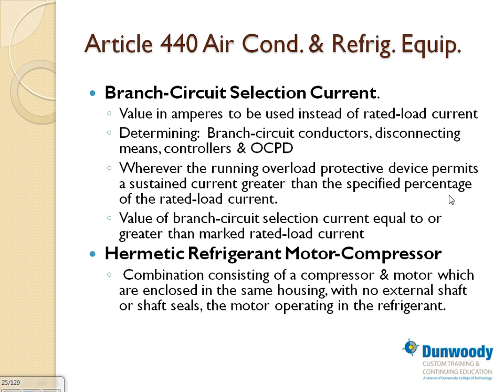HVAC, let me summarize HVAC equipment for you guys. If you have HVAC equipment, chillers are notoriously famous. Rooftop units. Chillers, rooftop units, condensing units. Two things you have to understand. Electrically speaking, when we size things, actually there are three things. Number one, you need to size a conductor. There's something called minimum circuit ampacity stamped right on the chiller, the compressor.